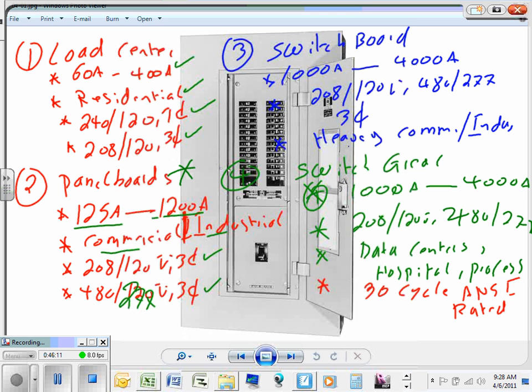I want to remind you, if you guys forgot, that the standard sizes of panel boards are located right in here. So we have panel boards, according to this guy, the panel boards go all the way to 600 amp. And these are what he called lighting panel boards. And then switchgear and switchboards go all the way on the other side here, which is 312 and 330. Any question, guys, about the panel board? So this is where we are. Camille, my friend, this is us. 125 all the way to 1200 amp.